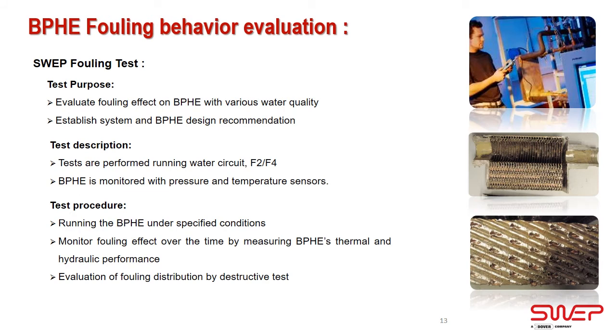How do we evaluate the fouling behavior of a heat exchanger? For that, we built a test rig in our lab where we can compare different heat exchanger designs under various water flow, water quality, and water temperature. Based on our test results, we are already able to draw some clear conclusions and boil them down to recommendations. One of them is a recommendation about minimal shear stress value for various water qualities. The worse the water quality, the higher the shear stress value must be.